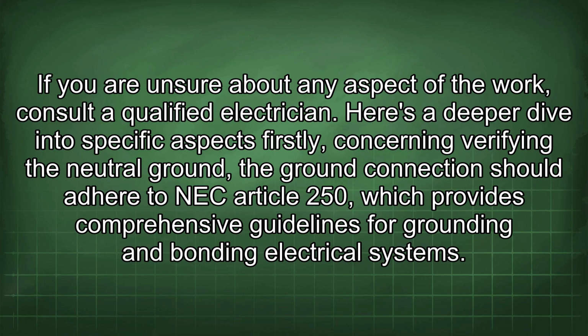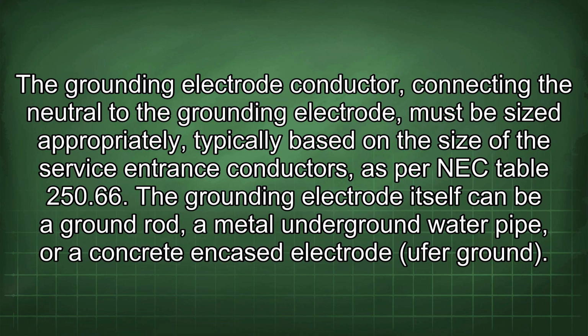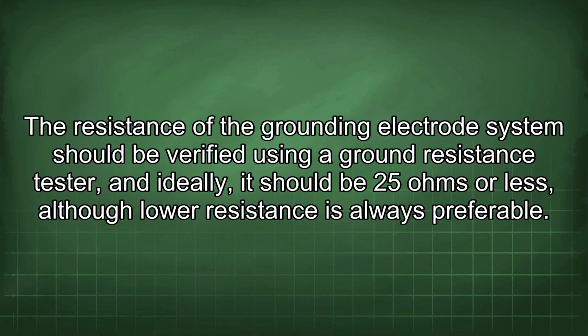Firstly, concerning verifying the neutral ground. The ground connection should adhere to NEC Article 250, which provides comprehensive guidelines for grounding and bonding electrical systems. The grounding electrode conductor connecting the neutral to the grounding electrode must be sized appropriately, typically based on the size of the service entrance conductors, as per NEC Table 250.66. The grounding electrode itself can be a ground rod, a metal underground water pipe, or a concrete encased electrode (ufer ground). The resistance of the grounding electrode system should be verified using a ground resistance tester, and ideally, it should be 25 ohms or less, although low resistance is always preferable.